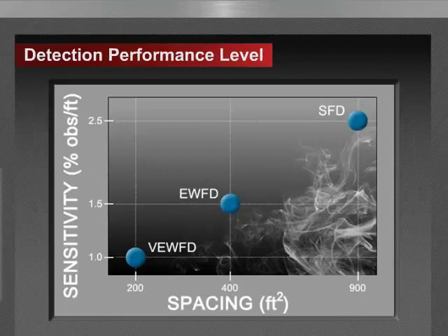So assessment of the risks and performance requirements specific to particular areas within IT communication facilities forms the basis for the level of protection applied in terms of sample point density and nominal sensitivity, as we discussed. So in Part 1, we introduced 3 acronyms referenced in performance codes such as NFPA 76 and industry practices. And those were more specifically SFD, which refers to standard fire detection with spacing at 900 square foot and alarm sensitivities typically at that stated by the device's listing.